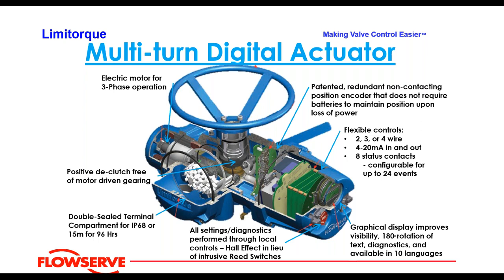Some positives of this style actuator: it is sealed with O-rings, providing a double-sealed terminal chamber. If there is condensation or leakage through a conduit line, it will get into the terminal block but not back into the actuator where the electronics are held. This actuator is rated IP68 for temporary submersion of 15 meters for 96 hours, compared to an electromechanical actuator which might be rated for one meter for 20 hours.